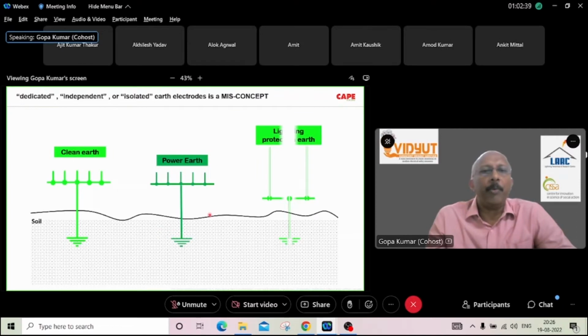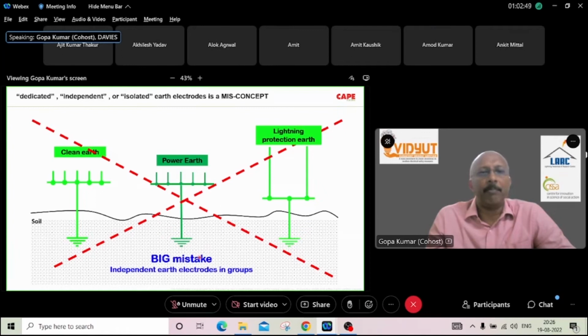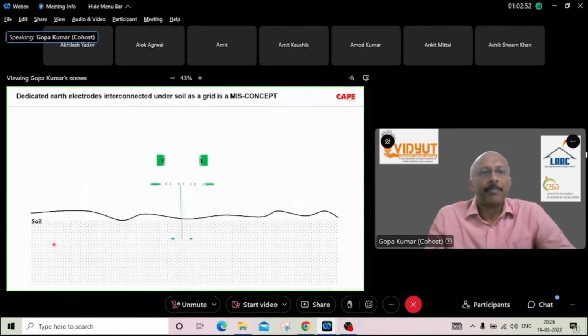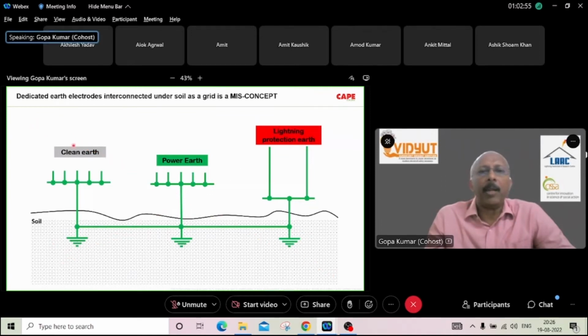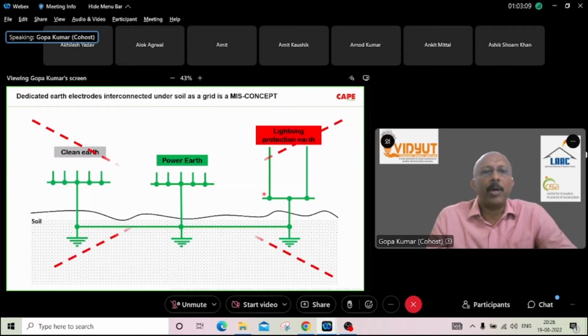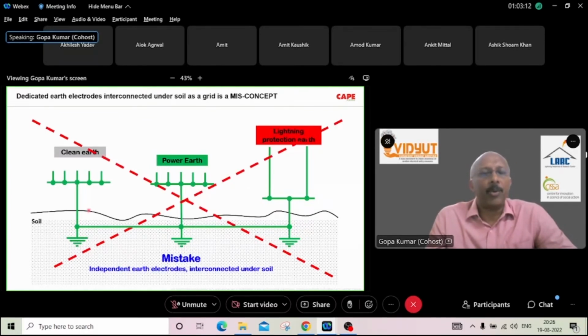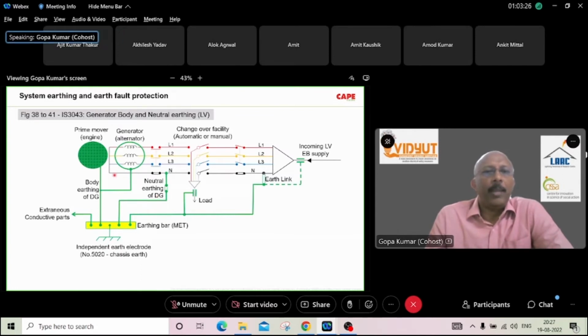Number two, a group of equipment like electronic items and UPS connected to a separate earth electrode in soil, power earth separate, lightning protection separate. This is also absolutely a mistake. Number three, there are separate clean earth, power earth, lightning protection earth. Then sometimes people are very proud to say that without informing the electrical inspector, I interconnected everything under the soil. Please note that this is also a foolish idea. This is also never written or documented in any of the documents in India. These are misinterpretations. What is written is, for example, you are seeing a picture from the IS 3043.